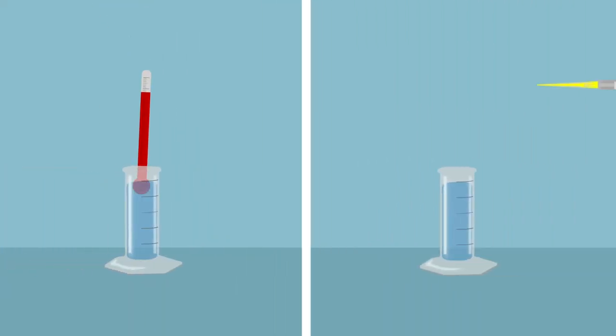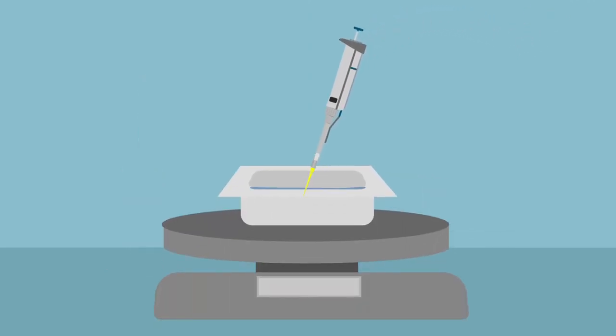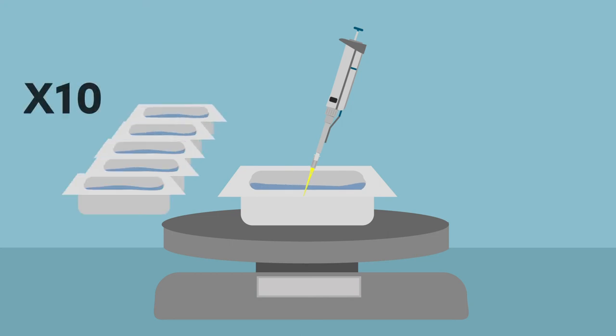Check your water temperature. Pre-rinse your pipette tip and immerse the tip 2 to 3 millimeters into the liquid. Pipette the liquid into the boat. Weigh it and then repeat the procedure.